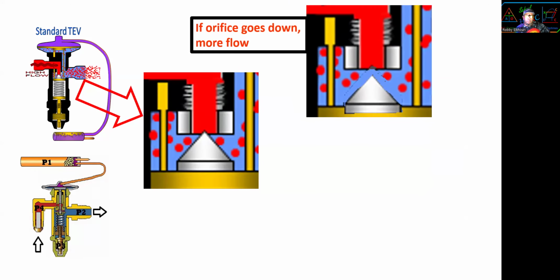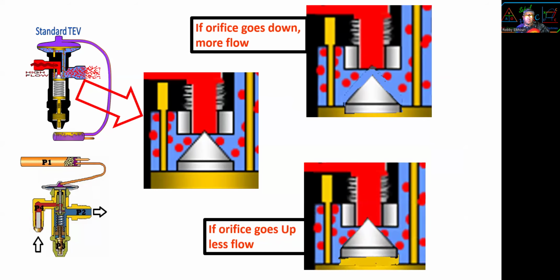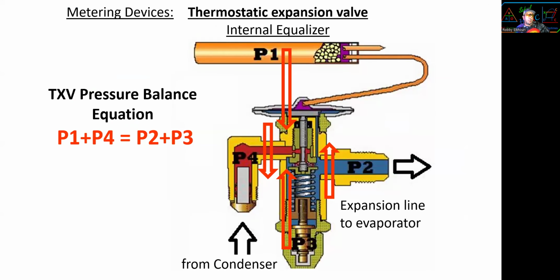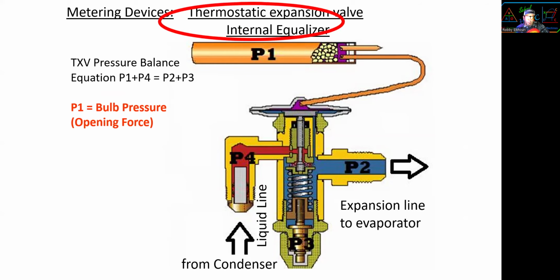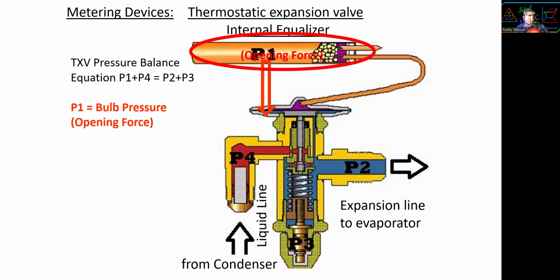If orifice goes down, more flow. If orifice goes up, less flow. Now let's go about the thermostatic expansion valve. The pressure P1 plus P4 equals P2 plus P3. All right, first, P1 is the pressure of the bulb, and that's the opening force, push down to open.